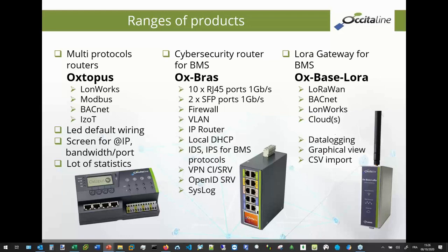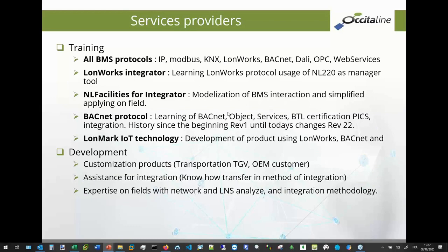We have the third and last range of product. It's the Ox-Base-Lora. In fact, we work on the LoRaWAN network, and with this device we can create a local network, connect and manage different generic sensors in LoRa, and propagate and convert this LoRa data point information to BACnet or to LON, and we can send it to the cloud for different usages. This third product can data log each piece of information. It includes a very simple graphical view with a trend, and we can export the CSV for all data points if you want to use that externally.